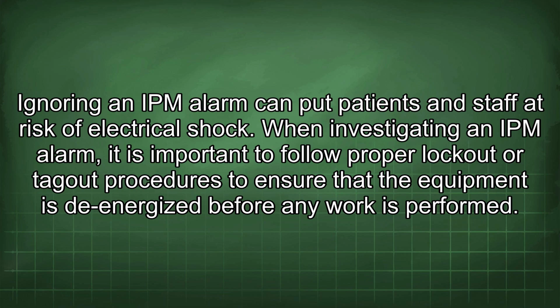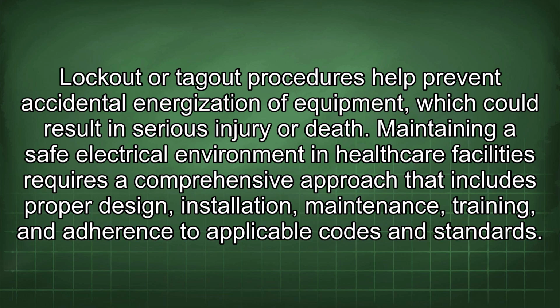When investigating an IPM alarm, it is important to follow proper lockout or tagout procedures to ensure that the equipment is de-energized before any work is performed. Lockout or tagout procedures help prevent accidental energization of equipment, which could result in serious injury or death.